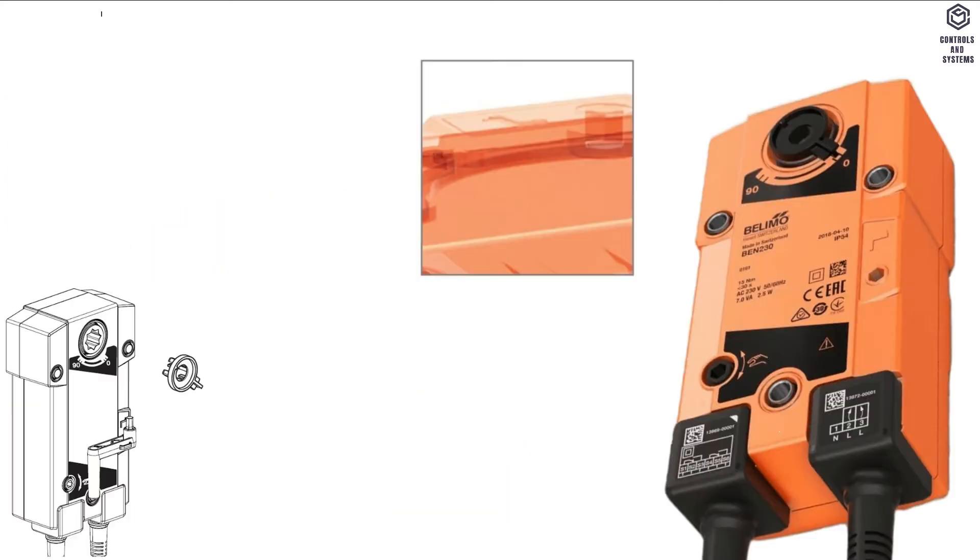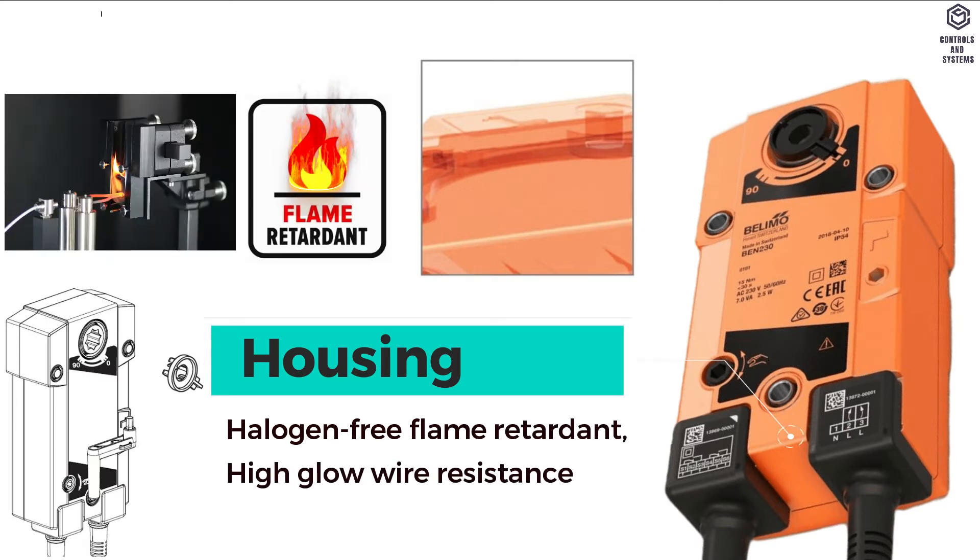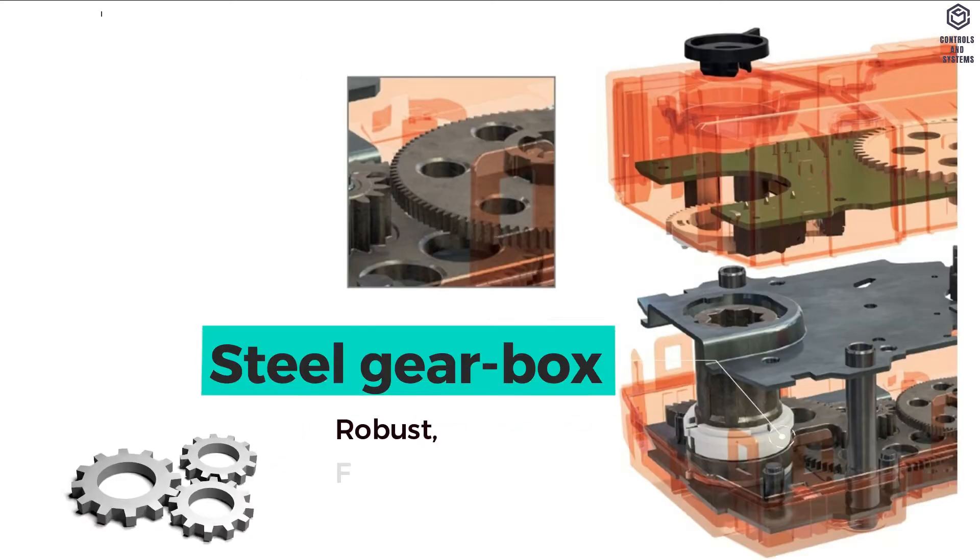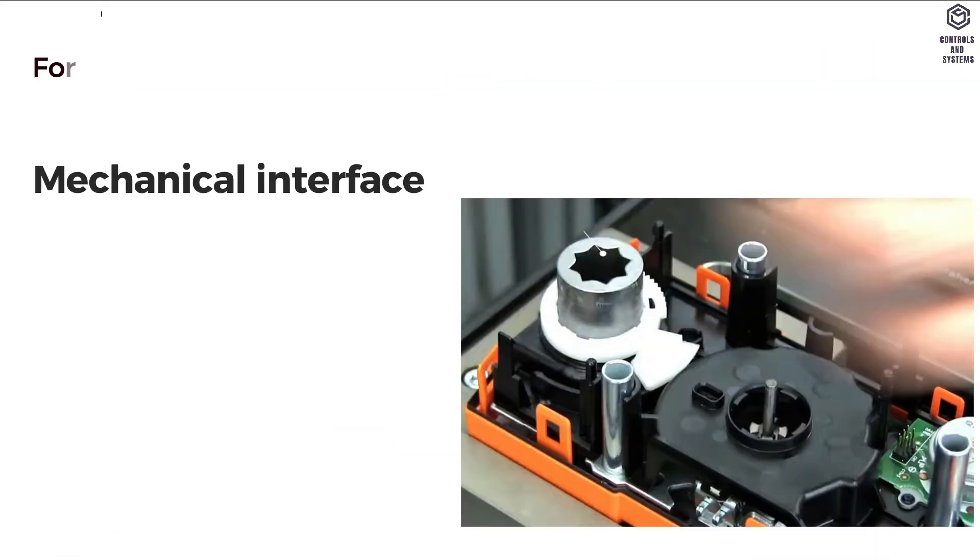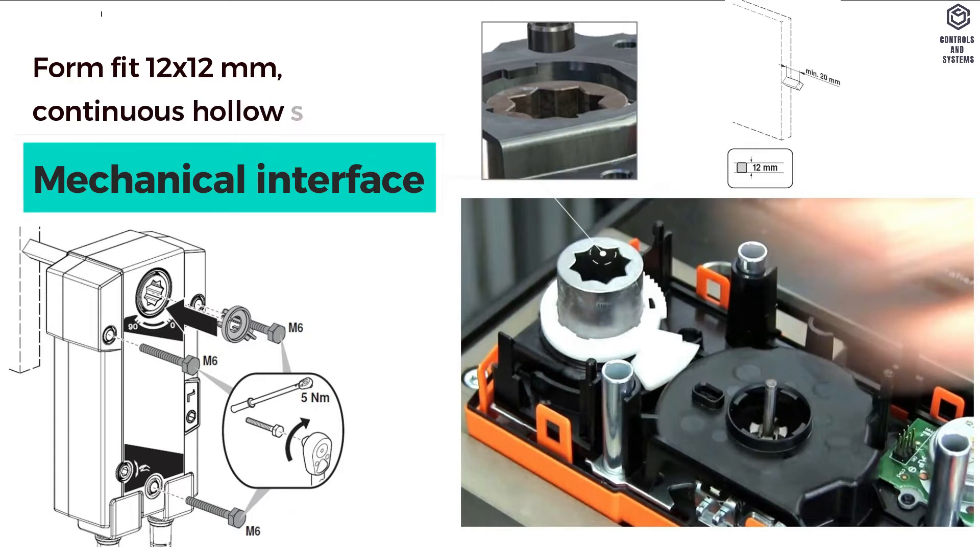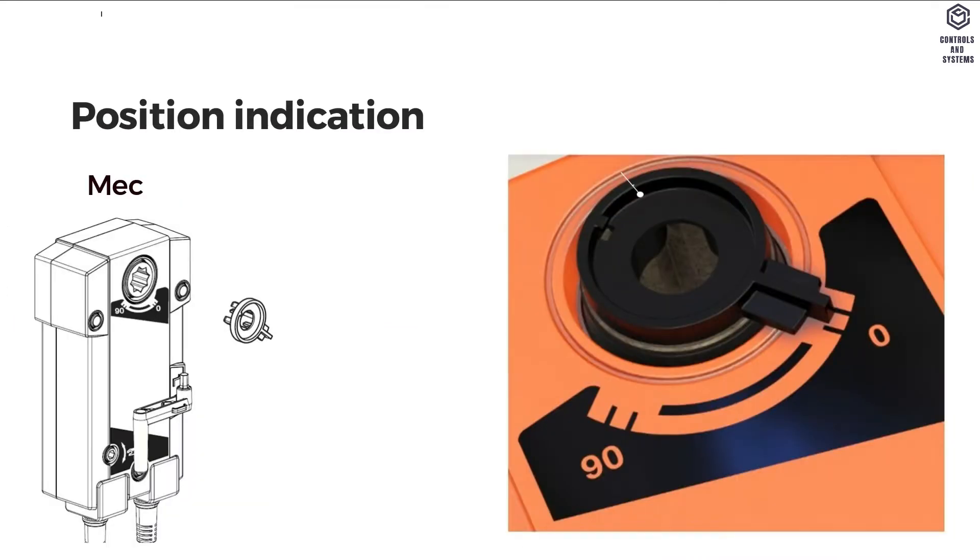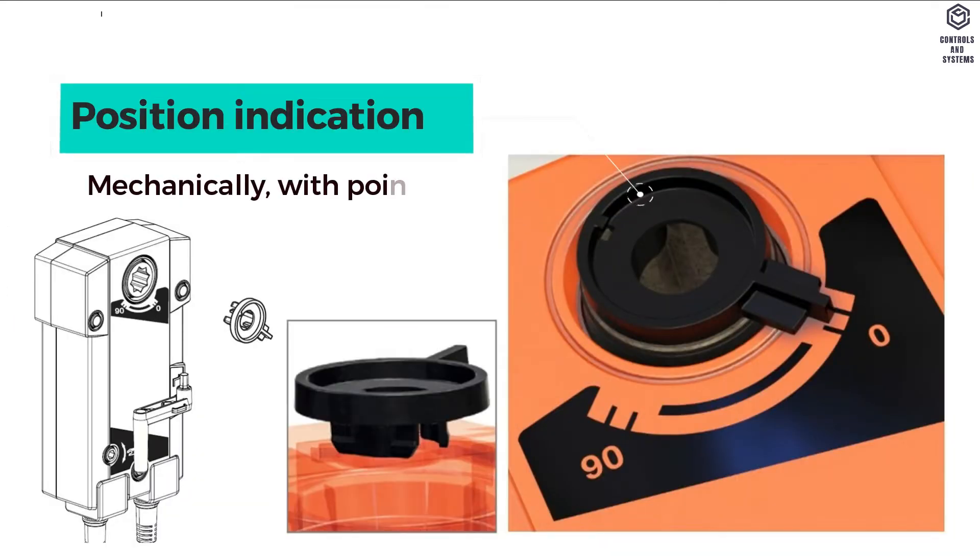Material data: housing is halogen-free flame retardant, high glow wire resistance. Actuator steel gears are robust and fire resistant. Mechanical interface is form fit 12 into 12 millimeter, continuous hollow shaft. Manual override is possible with hand crank. Position indication is mechanical with pointer.